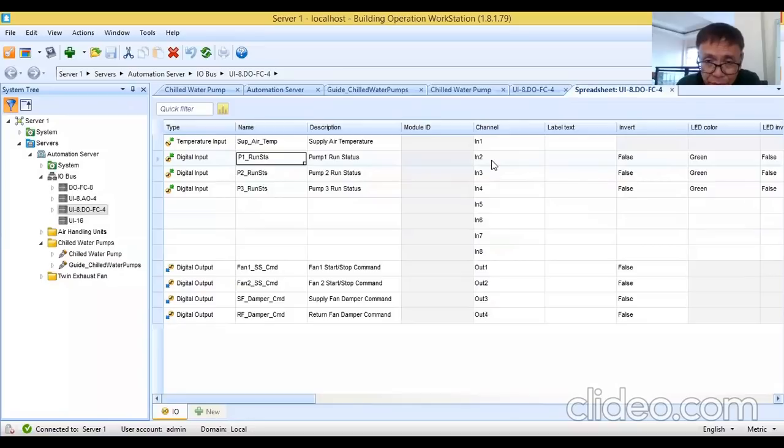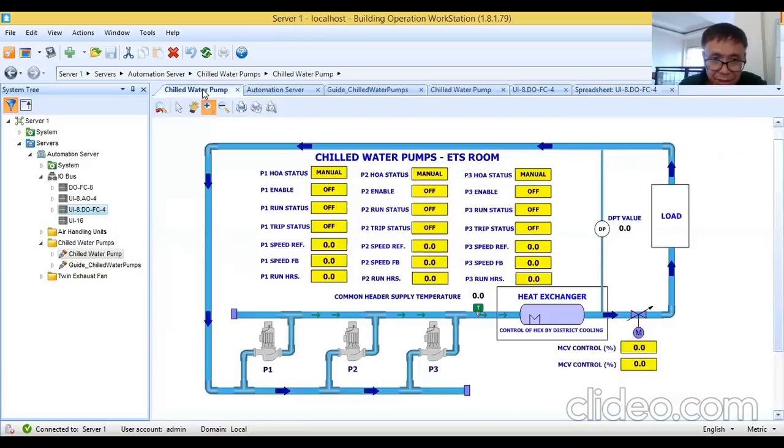Now what your technician will do from this I/O module channel 2, they will pull a 2-core cable. Then that cable from the DDC will go to the control panel of the pump. Then they will look for the BMS points provision from the panel fabricator. Of course, as I said beforehand, you need to tell the electrical engineer who is responsible for the motor control fabrication that you need the following points. So you will say, okay, Mr.